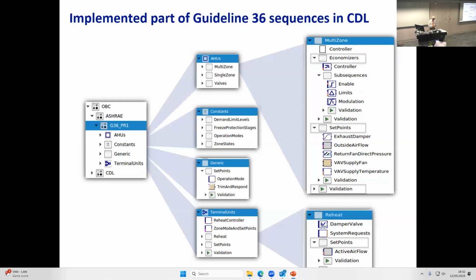This case study involves taking a control sequence from the ASHRAE Guideline 36 that I mentioned, and casting it into this neutral format, an executable language called CDL, or Control Description Language. So you're going from natural language - the ASHRAE guideline is written in regular text, like 'this actuator will do such and such in response to whatever' - and that has to be turned into executable code, which is what the control hardware needs in order to do its job.